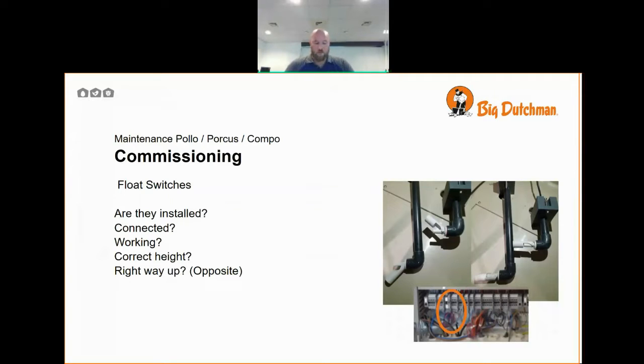During the active phase of the commissioning, test the floats. With the power on, lift the maximum float. The high level water alarm on the front of the panel should light up. Let the float drop back to level. Press the reset button on the panel and the alarm must reset. With the pump running, press the minimum float down to simulate a low water level. Pump must shut down and display the alarm dry run.